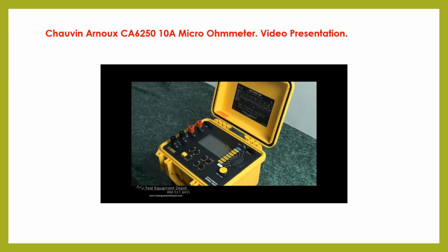The AEMC model 6250 micro-ohmmeter is unique in that it can measure out to 0.1 micro-ohm. That is extremely sensitive and probably perhaps the best in the industry. It can measure up to 2,500 ohms, so it does have a broad range, although normally it will be measuring down into the very low ohm resistance.